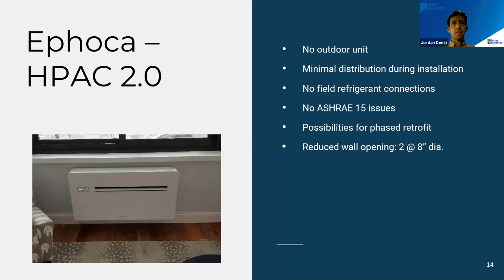This is a new heat pump from Italy called the Ephoca HPAC 2.0, and there are a couple of similar products out there. It's basically an indoor unit that hangs on the wall with two pipes going through the wall, so there's no outdoor unit—this would be a package system. It contains the same technology as mini splits, meeting those efficiency levels with a VRF compressor, variable speed compressor and fans, and sophisticated controls to achieve high efficiencies and capacity at all outdoor conditions.